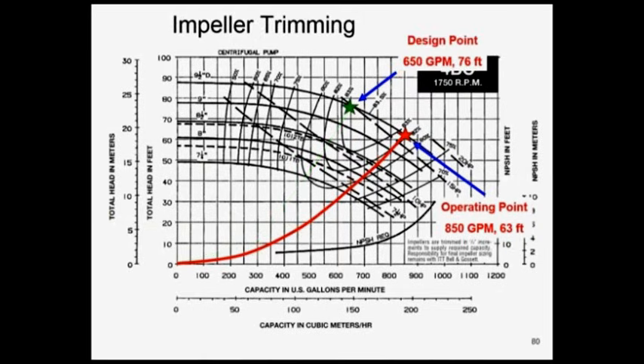So all we got to do is come along and say, okay, we're really running on that red curve, but not on the other one. Our real system curve is 850 at 63. Now all I really need is 650 GPM. See that vertical line? All I got to do is strike a vertical line up at 650 and see where it crosses my real system curve. And it crosses, help me out there, somewhere about 7.5 inches, something like that, maybe a little less. We'll figure out exactly in a minute. But that's a new impeller size that we need. Look at the horsepower. Horsepower is down a little bit over what, 7.5? Wow. We dropped the horsepower way down.